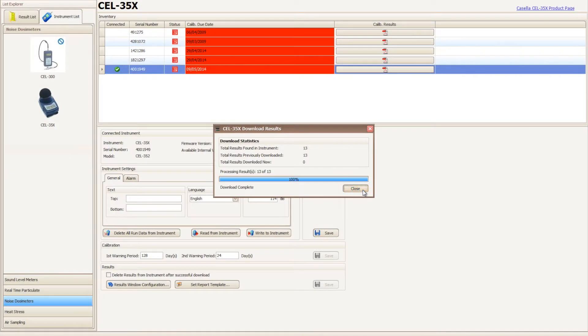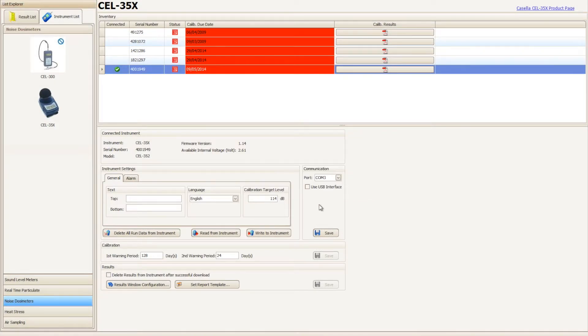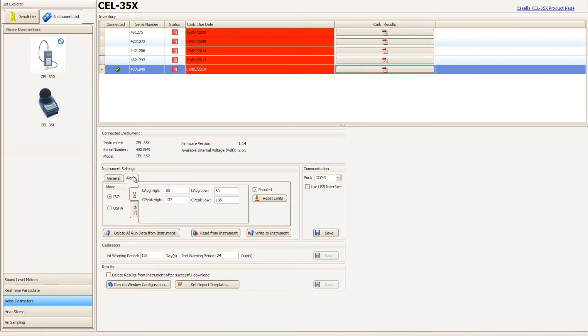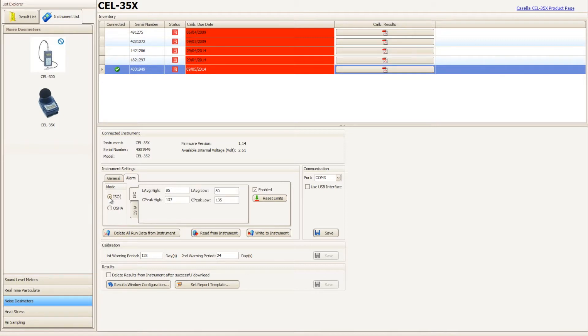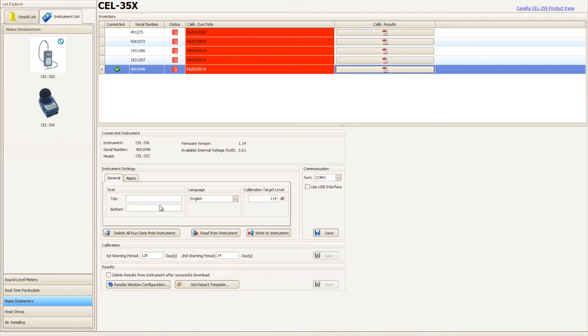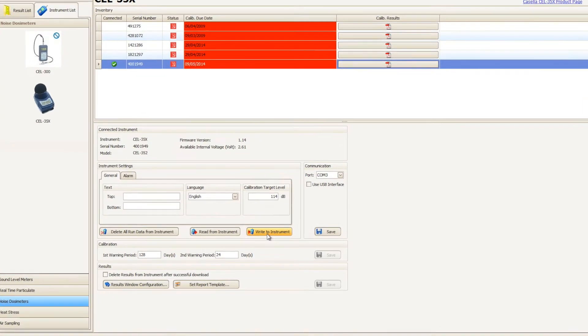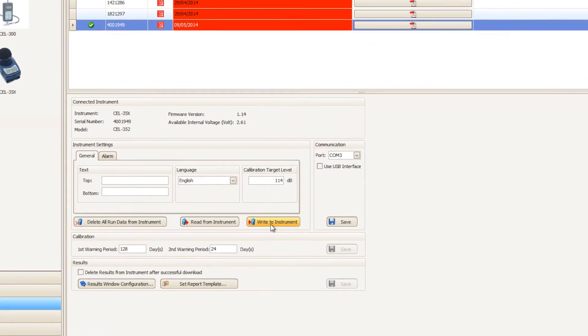Once the download process is complete, make sure that the instrument settings are correct as they will be written to the instrument. Once happy that the instrument settings are correct, locate the write to instrument button underneath the instrument settings box.